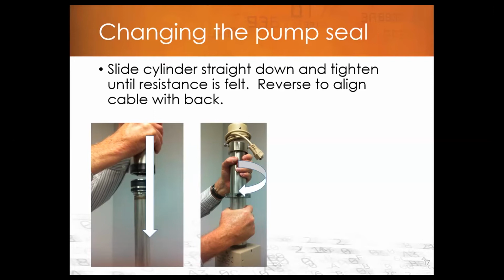One thing I would recommend, though, before you put the cylinder on, is to inspect the inside surface of the cylinder. You can take a flashlight or a cell phone light and go ahead and shine that down on the inside surface of the cylinder. What you're looking for is to make sure that you don't have any scratches or score marks on the inside surface of the cylinder. Basically, when you look inside the cylinder, it should be a mirror finish with no deep scratches or score marks, anything like that.